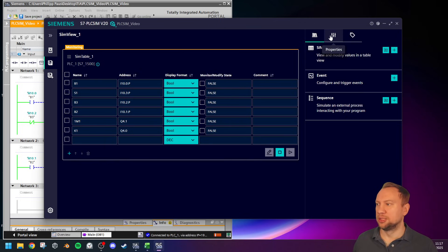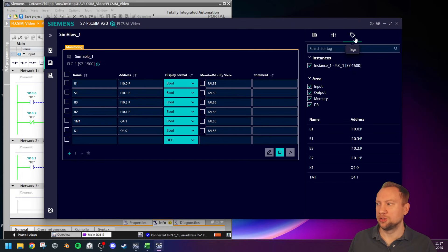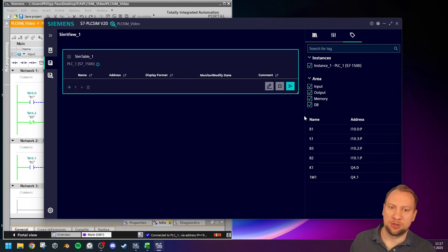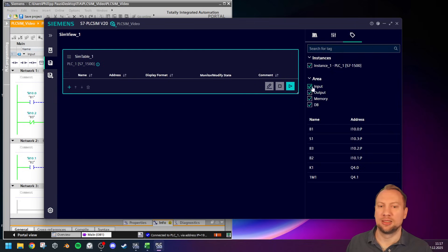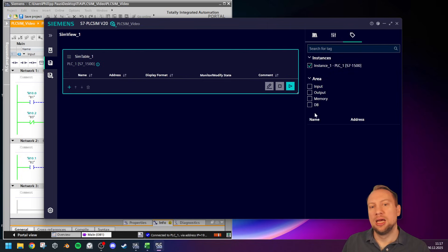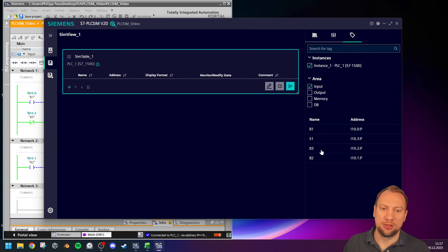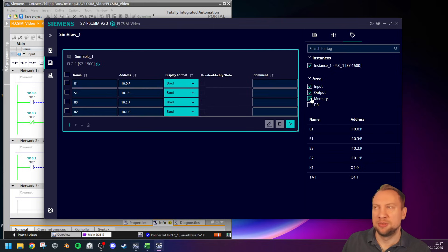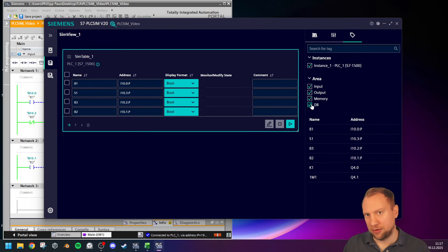You are more powerful than your program with the simulation table. You can create multiple simulation tables on the right for multiple different test cases. Now on the right side you also have Properties and Tags. If you click on Tags, you can select the PLC — I only have one instance. I can filter to show just inputs or outputs, and clicking on a tag will automatically integrate it into the sim table. The same works for outputs, memory tags, and data block tags.